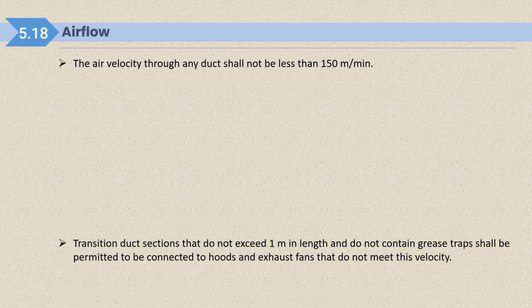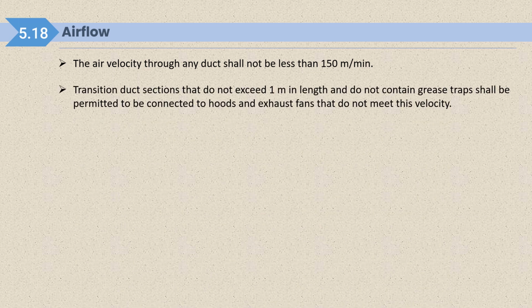Now we are in airflow 5.18. The air velocity through any duct shall not be less than 150 meter per minute. So this is the air velocity that we have to maintain inside the duct. Transition duct section that do not exceed 1 meter in length and do not contain grease traps shall be permitted to be connected to hood and exhaust fan that do not meet this velocity. So transition duct section that do not exceed 1 meter in length, it is permitted to be connected.